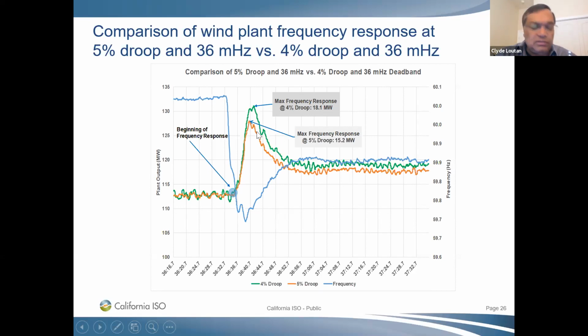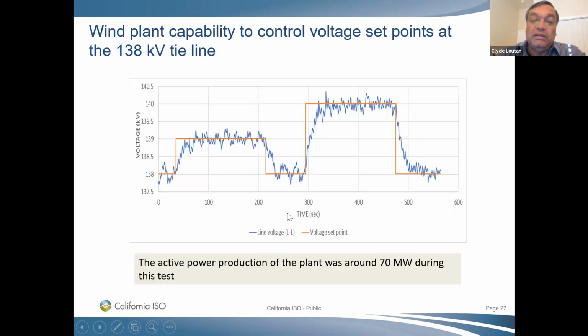So this is one of the things the California ISO is contemplating. We want to recommend all inverter-based resources operate at a 4% droop setting. We're also thinking of recommending a 16.7 millihertz deadband as opposed to 36, which is something that we're going to take to stakeholders and recommend either at the end of this year or early next year, only because you need the controllability and you have inverter-based resources. They're sitting there, no moving parts, everything is software, and they can provide the additional controls that you need.